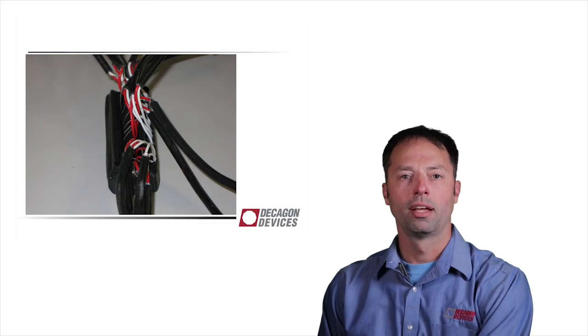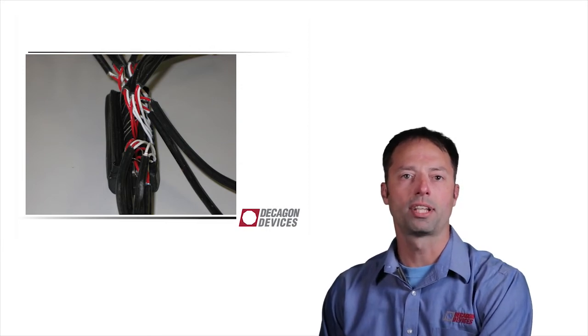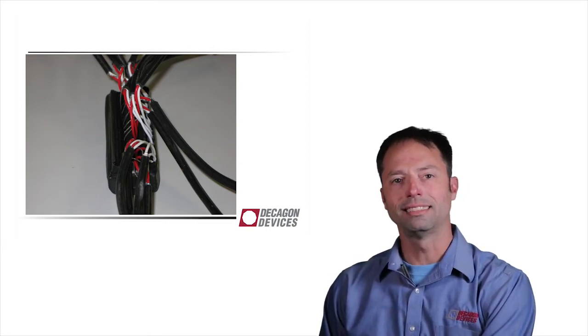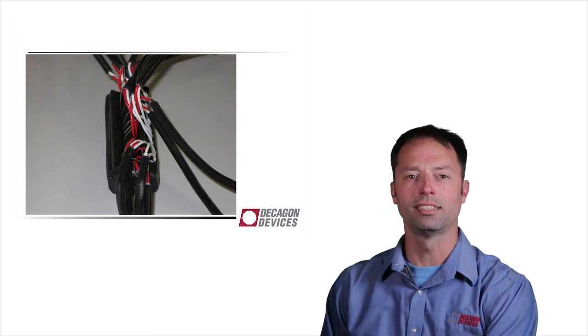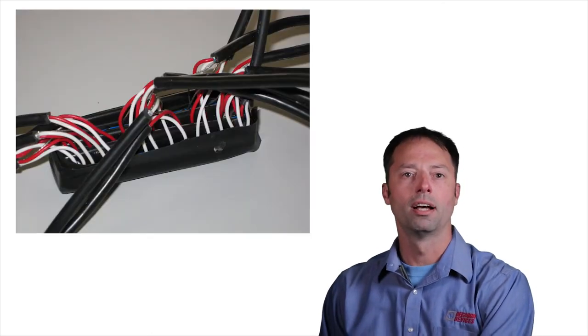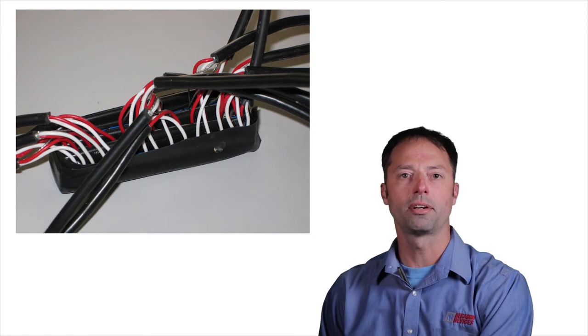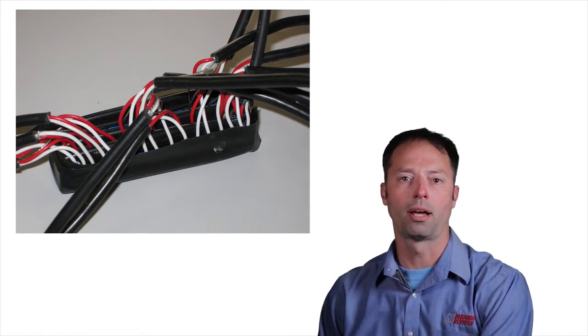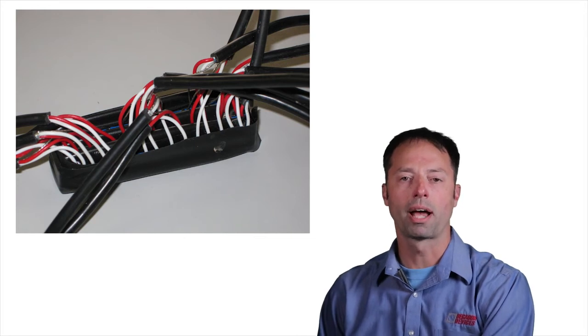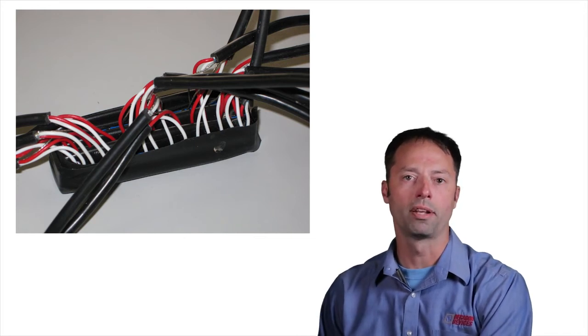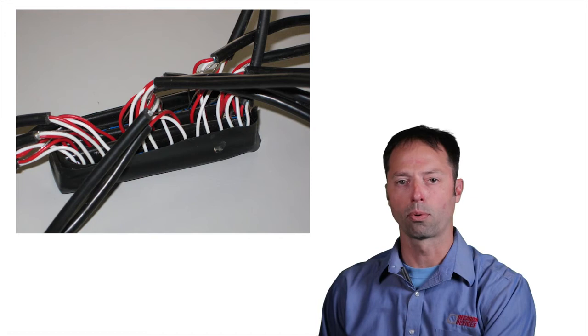Okay, here's another example of a homemade bus. This is something whipped together by our techs in our R&D lab. It's not the best bus ever made. Troubleshooting anything in here is going to be problematic, but it does accomplish the function of combining all of your sensor wires into one so that you can run it to a data logger port.